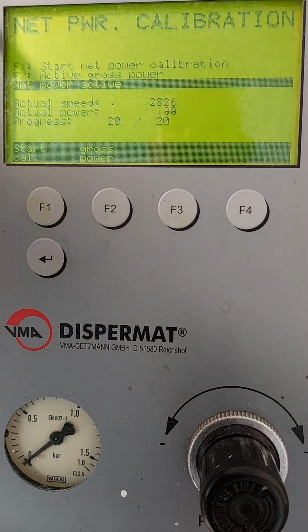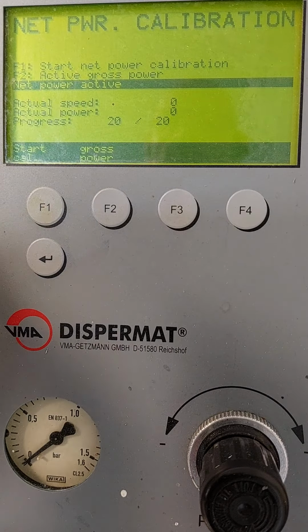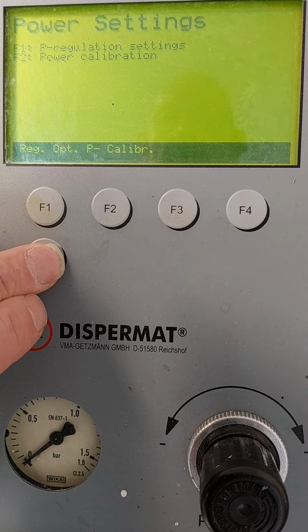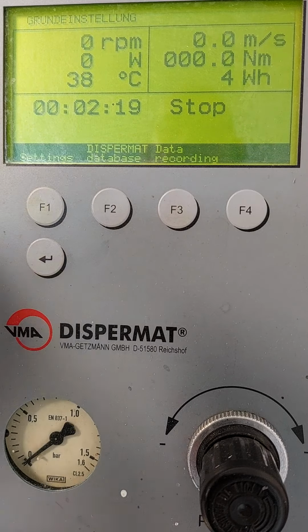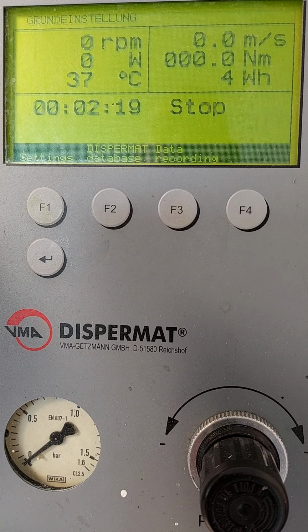So now we can see the calibration has been completed, net power is active, and if we press the return button, we return to the standard screen without the plus next to the power, so that any time we run now, if we run the mill, let's just enter a speed, 2,000 RPM, enter and start. We're now running without product, we're pulling 0 watts. So any power that goes in now is related to the actual milling performance that's going and the power that's going into the product itself.